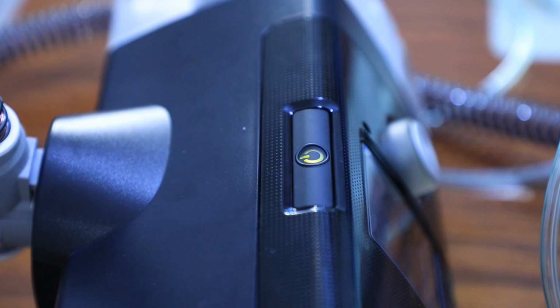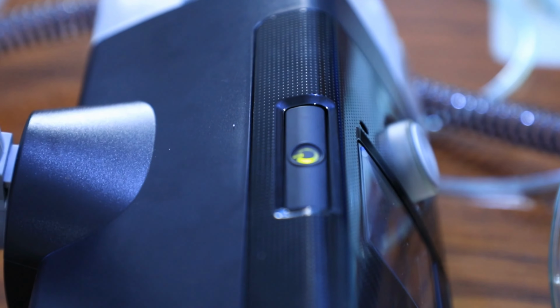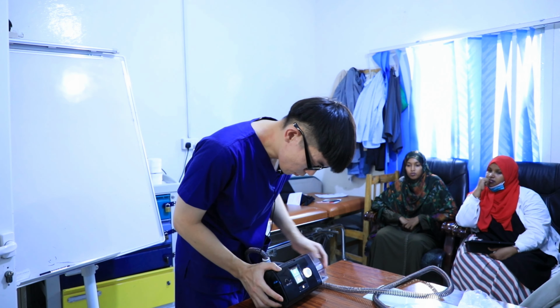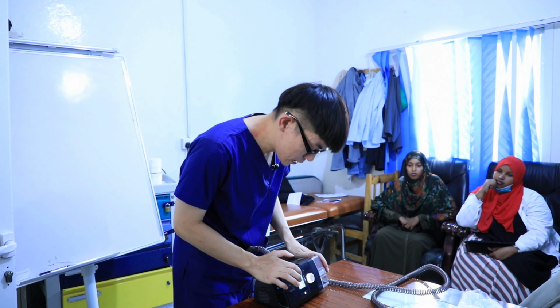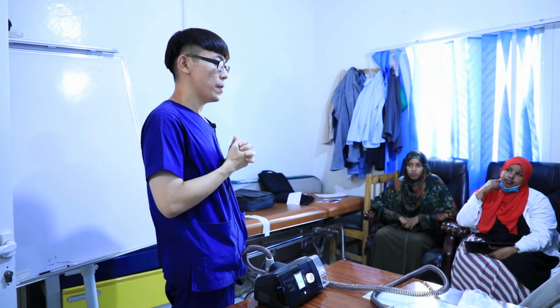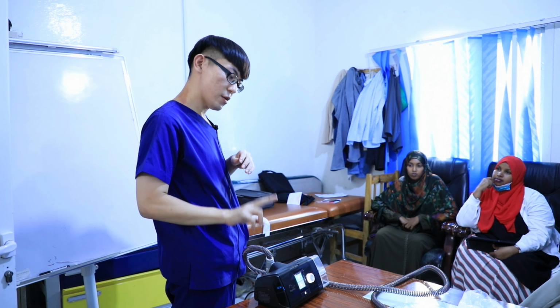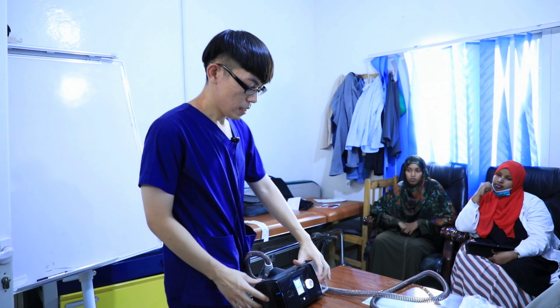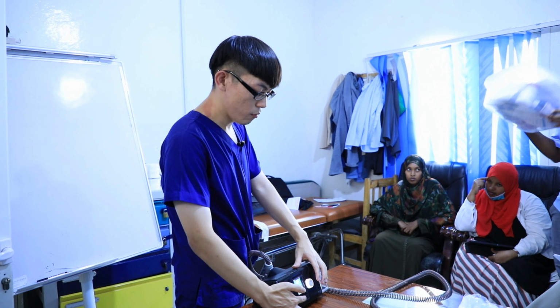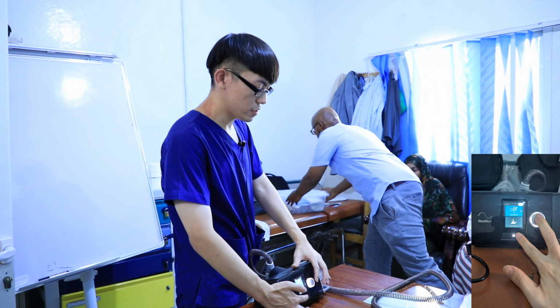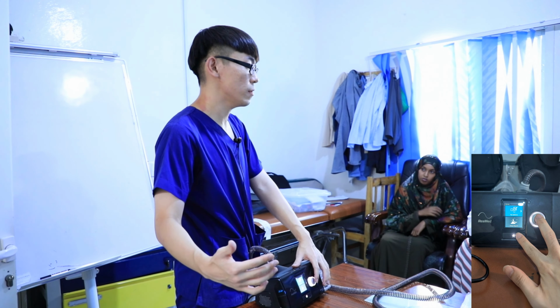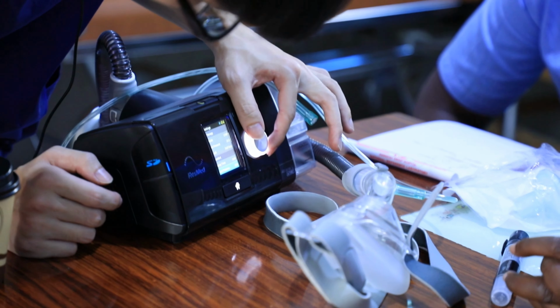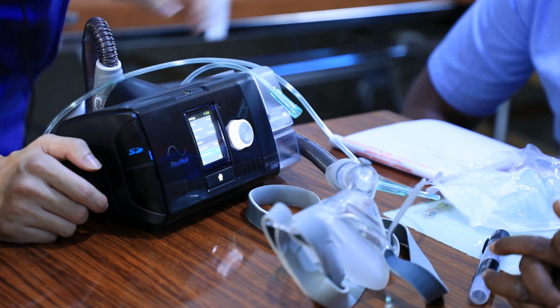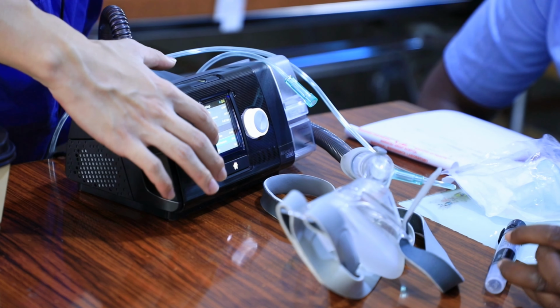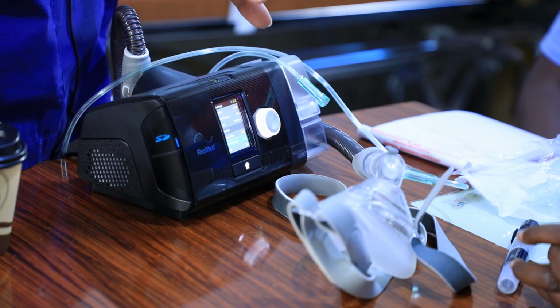Let's see. Usually when we plug in, it automatically switches on, and if not, we can press this button. We can see they have the menu over here, but because we would now like to set up, there is one secret about this ventilator: press this knob, and this is a home page button. Press these two buttons together to enter the clinical menu. This menu is for the patient or the family member only, so we need to enter another mode. Press these two buttons together and wait for 3 to 5 seconds.